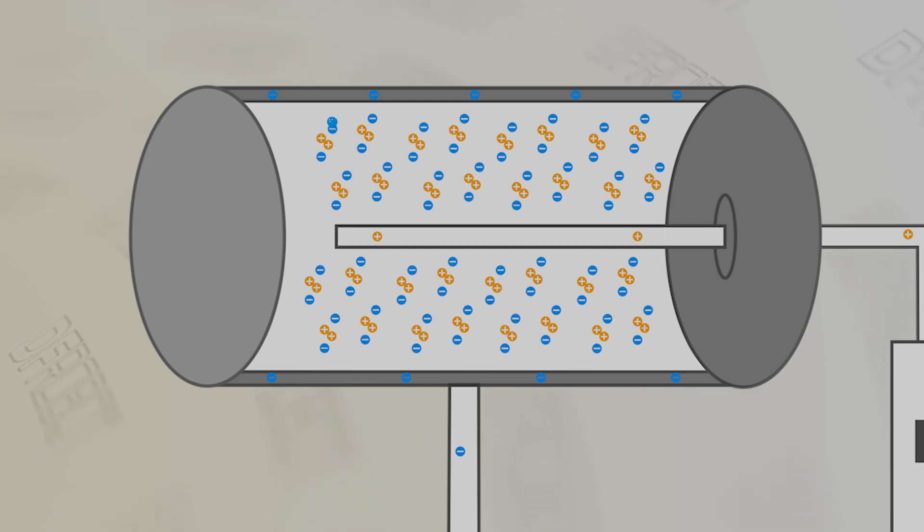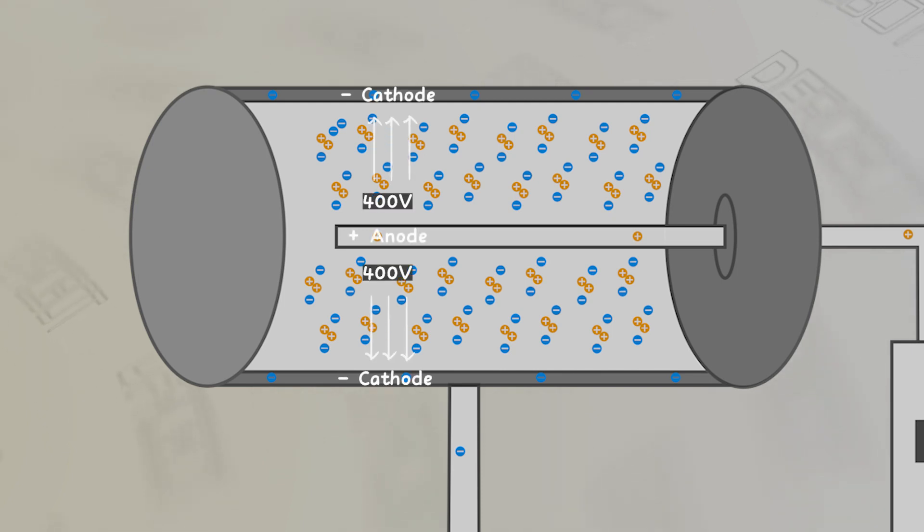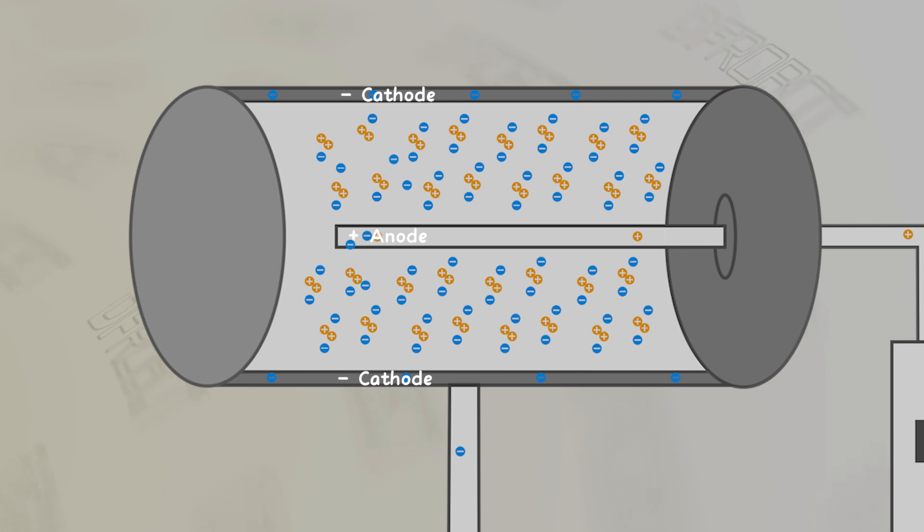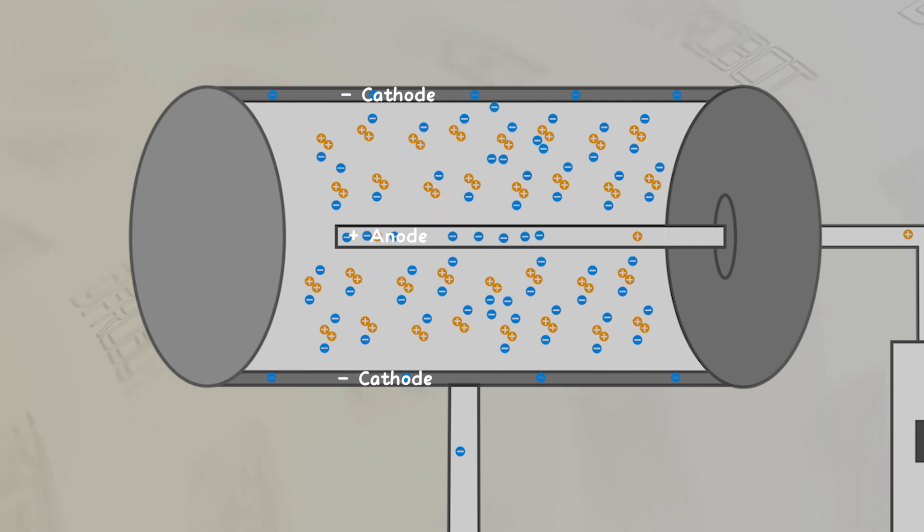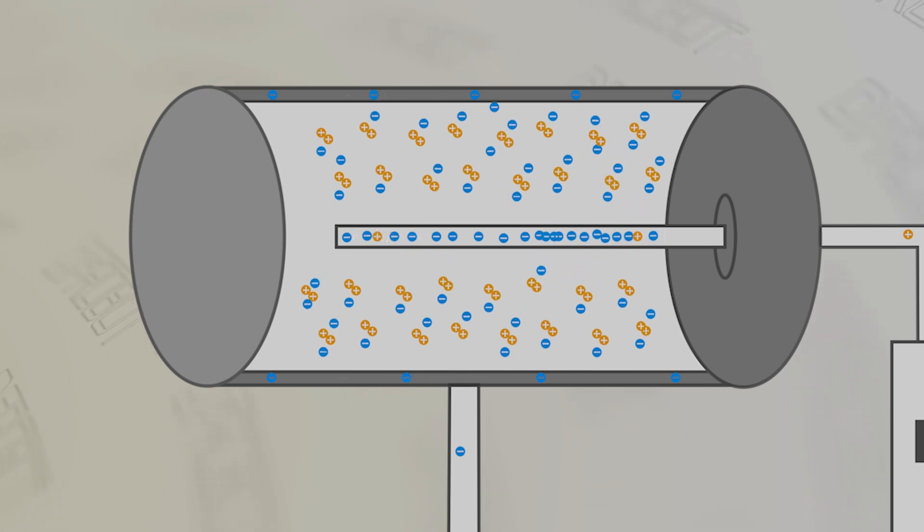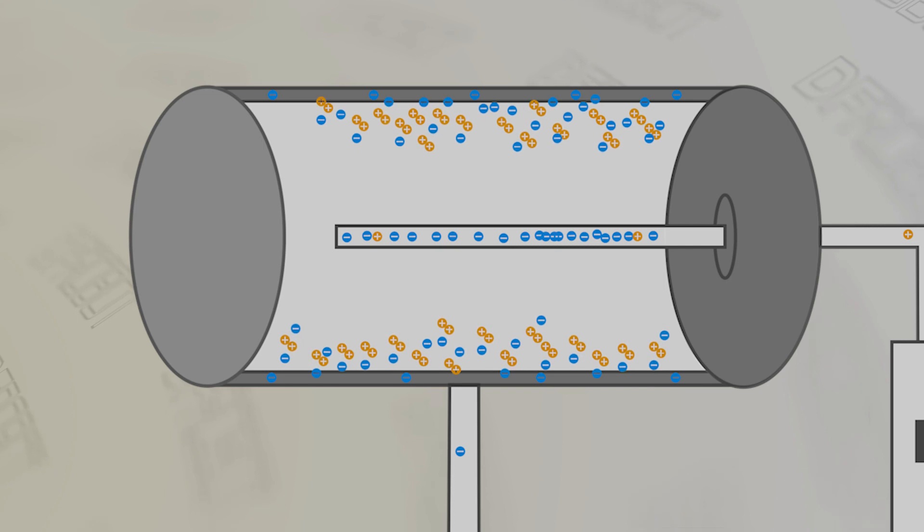Due to the high voltage present inside the Geiger-Müller tube, these electrons are attracted and move toward the central electrode. Along this journey, these electrons collide with additional gas molecules, causing more electrons to be released. This chain reaction, known as an electron avalanche, allows a single radiation particle to generate a multitude of electrons.